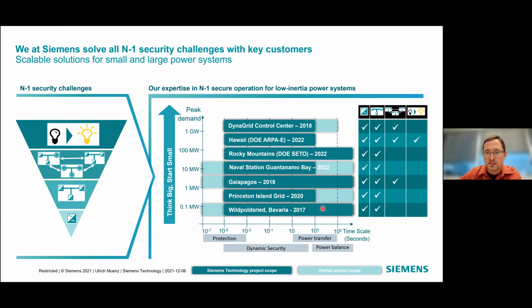We did a field test in 2017 in Bavaria, Germany, where a small part of a village, part of a feeder, was disconnected from the main grid, running as an islanded system supplied by 6 parallel grid forming inverters. This is our office building, which we converted into a microgrid that we can also run islanded for testing purposes. I mentioned the Galapagos project already, running since 2018 reliably, able to operate without any inertia when there's not enough solar generation.